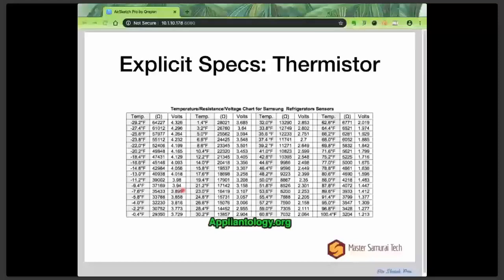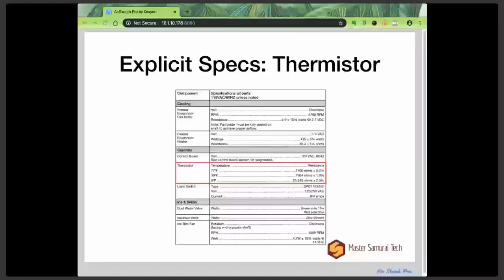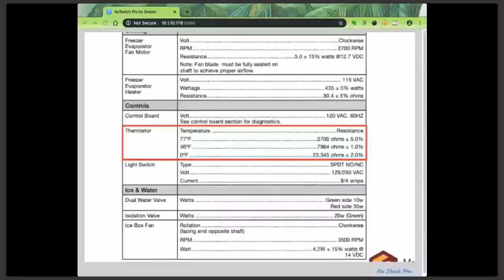Here's an example from a Whirlpool tech sheet, another example of explicit specifications. Again, we're looking at the thermistor here. They don't give you the granular resolution that Samsung does, just 3 data points, and they give it to you in ohms. Not ideal, but we work with the specs we're given. They also give you a little tolerance: this spec is 2,700 ohms, and this plus minus is the tolerance, so you're allowed a variance of plus or minus 5% on that spec.